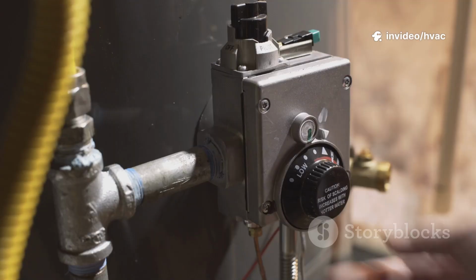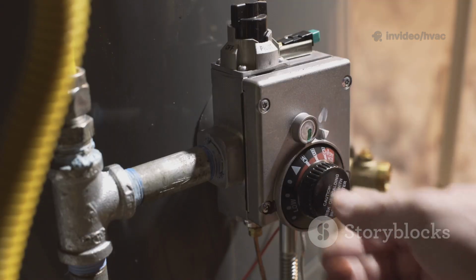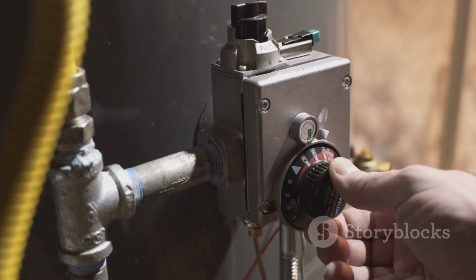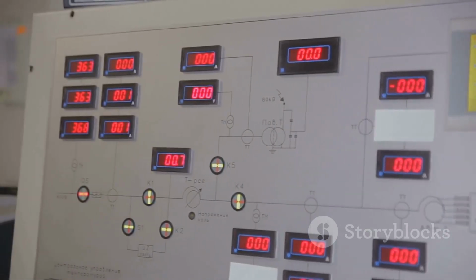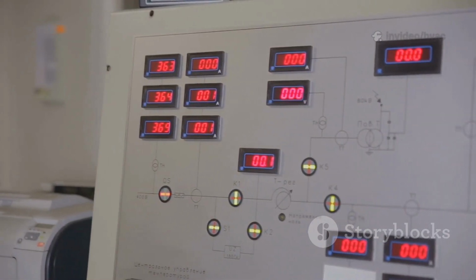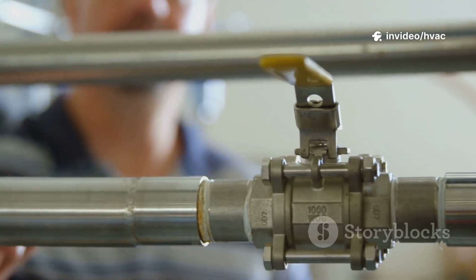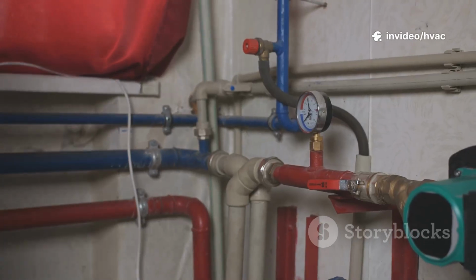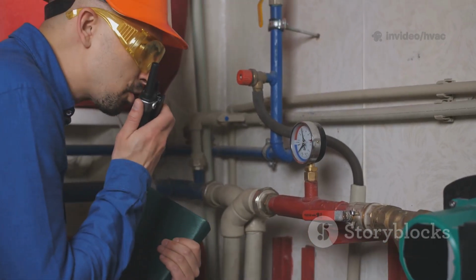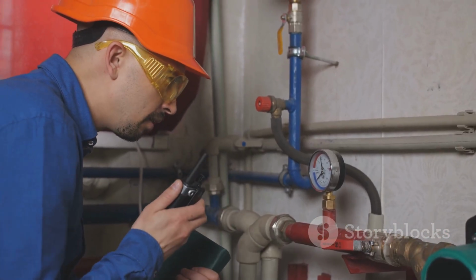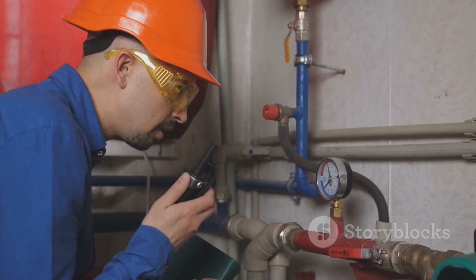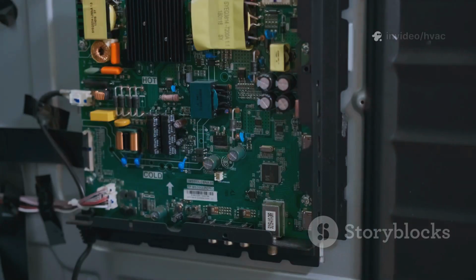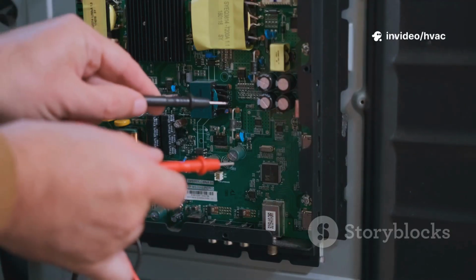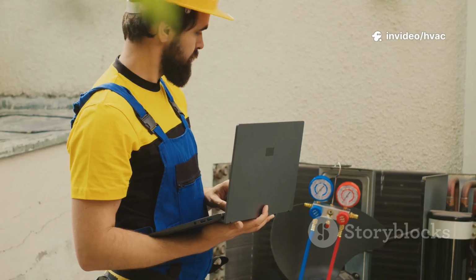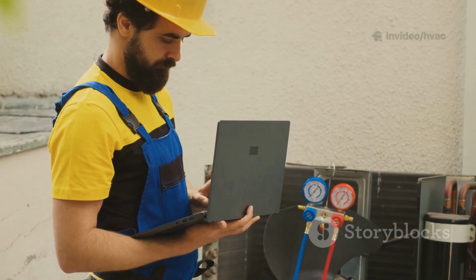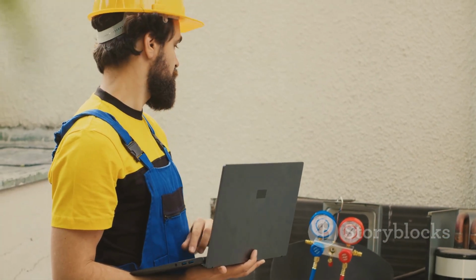associated with on-off control. A significant maintenance benefit of this integration is the ability of the BAS to provide feedback from the valve. Many advanced actuators can send a feedback signal back to the BAS, indicating the actual position of the valve. This is extremely useful for troubleshooting. For instance, if the BAS is sending a 10-volt signal to open a valve, but a flow meter in the system shows no water is flowing, the BAS can check the valve's position feedback. If the feedback shows the valve is closed, it could indicate a failed actuator or a wiring problem.